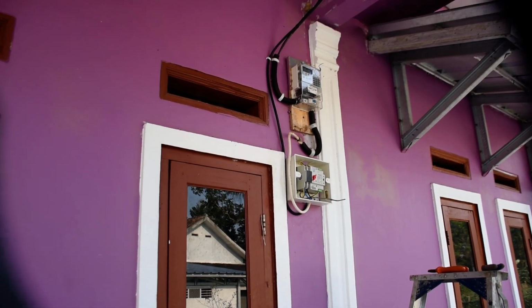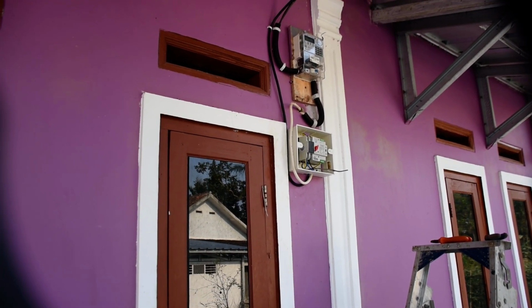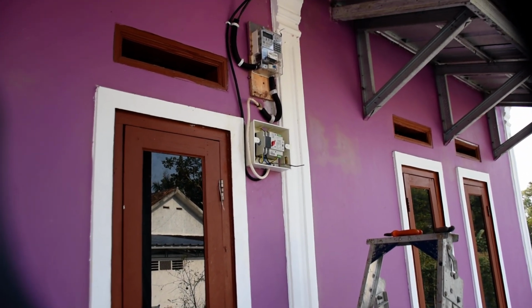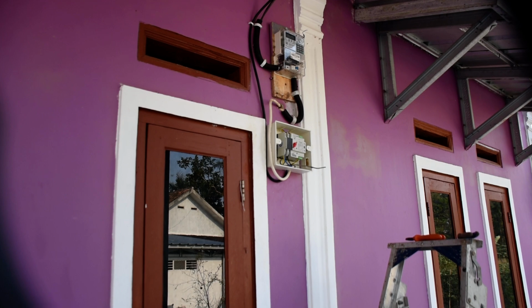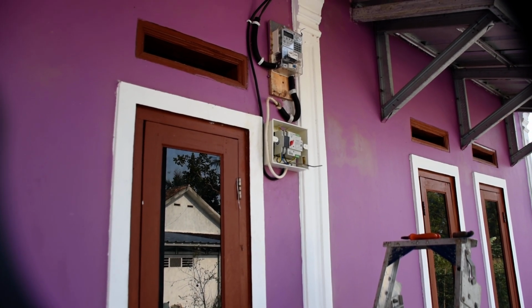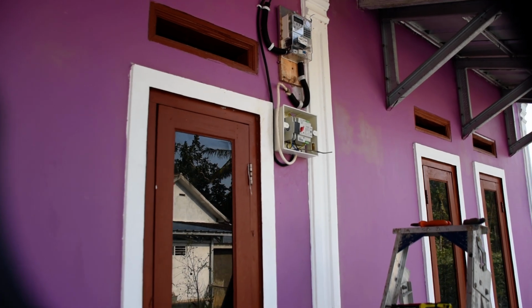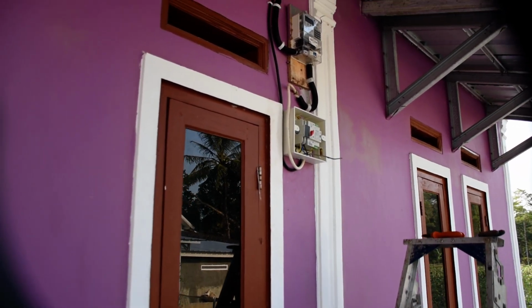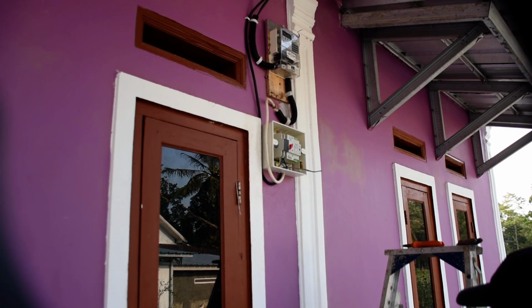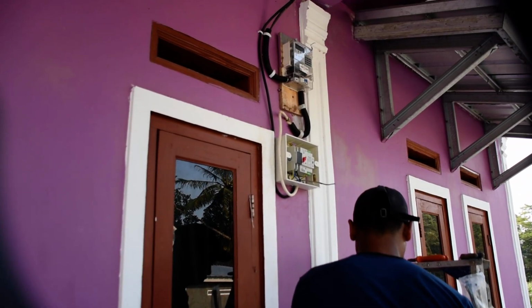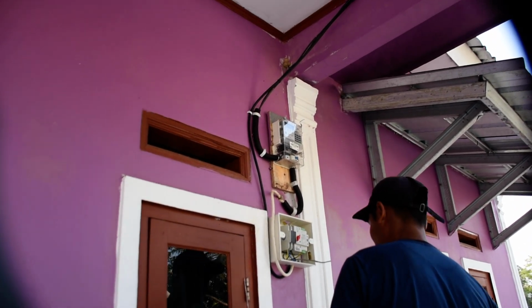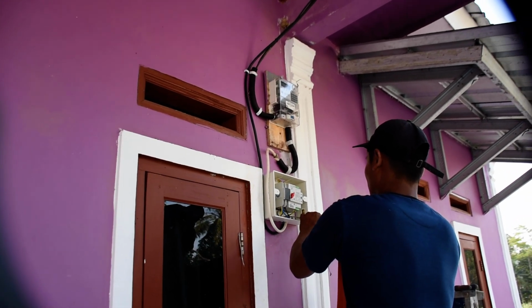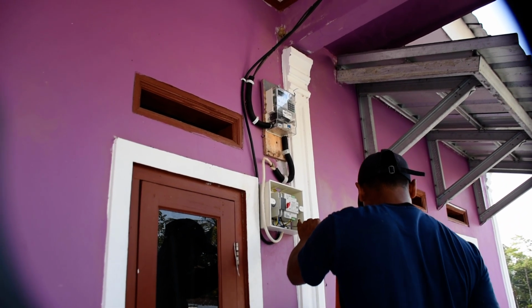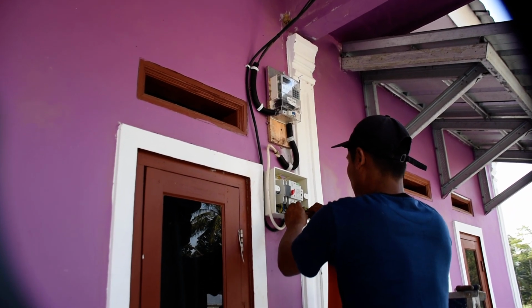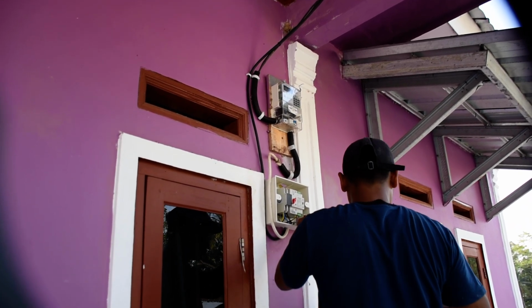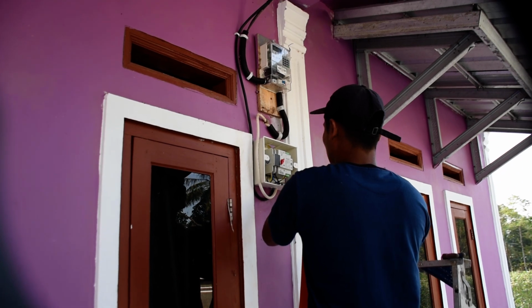We've got the black feed cable from the off-grid system at our house feeding into the inputs of the automatic transfer switch, and the lower white cable currently goes to the cutover switch inside, which can be eliminated. That goes to the output of the automatic transfer switch into inside, and then we'll disconnect the PLN cable from the cutover switch inside and connect it directly into the top terminals on the automatic transfer switch.